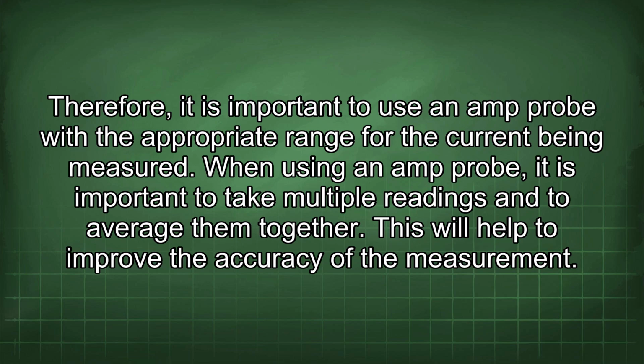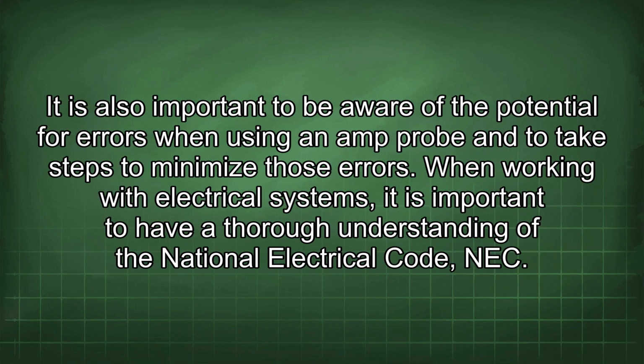When using an amp probe, it is important to take multiple readings and to average them together. This will help to improve the accuracy of the measurement. It is also important to be aware of the potential for errors when using an amp probe and to take steps to minimize those errors.